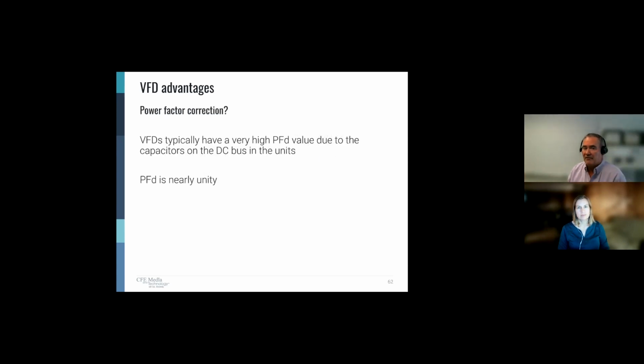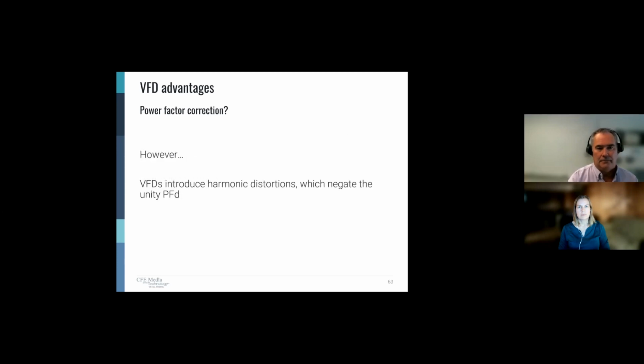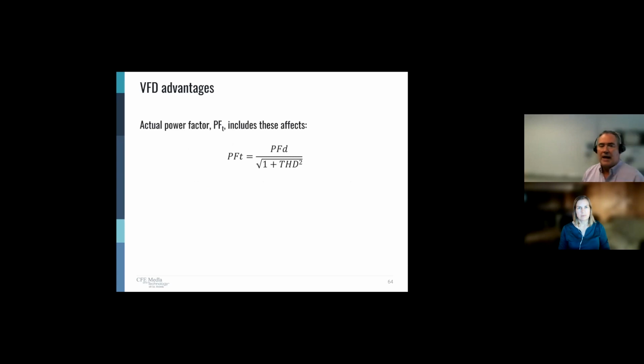We can also correct power factor with VFDs because they're not inductive when we connect them to the line. All they're doing is taking that AC and converting it to DC internally, and the power system doesn't see any of that. So they have a very high power factor. It's nearly unity for the most part. However, there's always a downside. VFDs can introduce harmonic distortions, which will affect that unity power factor. So the actual power factor has to take that into account, and you figure out what the total harmonic distortion is. That typically will come from the VFD manufacturer. You can do the math and figure out what your power factor is.